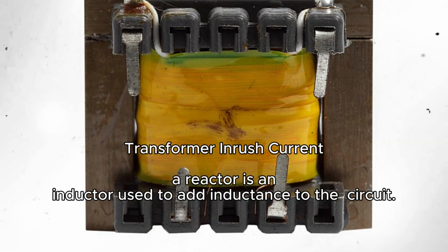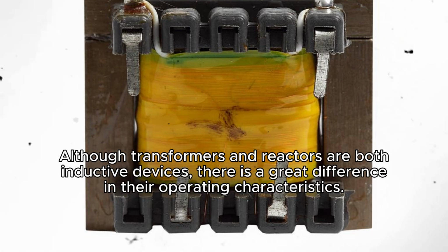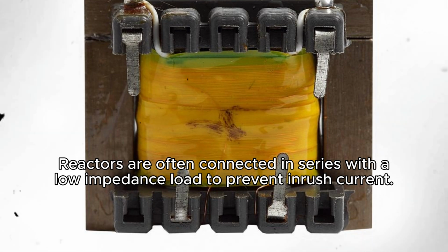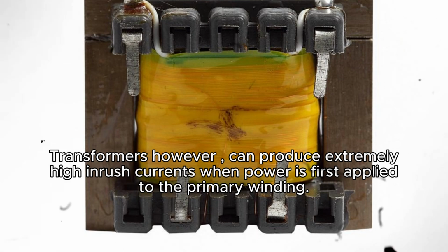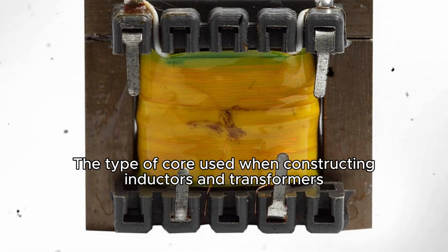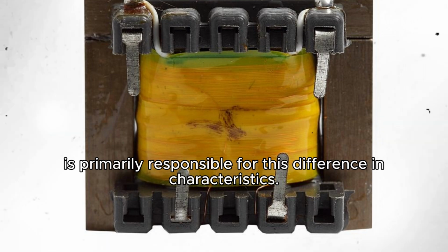Transformer inrush current. A reactor is an inductor used to add inductance to the circuit. Although transformers and reactors are both inductive devices, there is a great difference in their operating characteristics. Reactors are often connected in series with a low impedance load to prevent inrush current. Transformers, however, can produce extremely high inrush currents when power is first applied to the primary winding. The type of core used when constructing inductors and transformers is primarily responsible for this difference in characteristics.